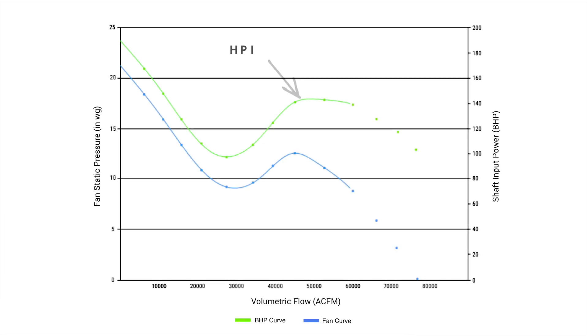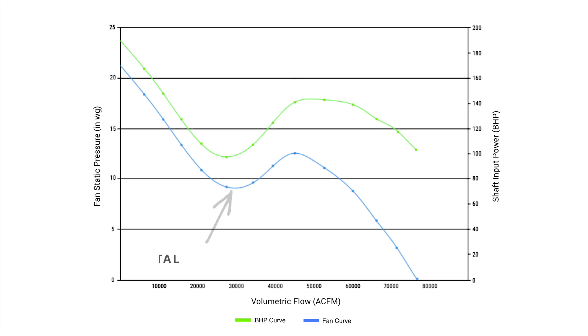Performance curves for axial fans have a non-overloading horsepower characteristic, meaning power consumption peaks and starts to drop off toward the wide open point of the curve. Axial fan curves also have a stall region located around the middle of the curve where performance is unstable.